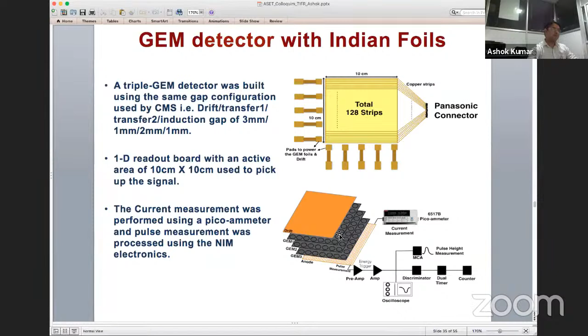And then we also measured the spurious signal rate, which is well within 1 Hertz for the 10 by 10 detector, and this is pretty good. And then we measured the MCA spectrum using the X-ray, and the last one is the gain. The gain is the important test. We have to see whether this is going to work in the region where we have very, very harsh environments. We need a very high rate detector. So we are seeing here that it can handle up to 4 kilohertz, and the gain is 10 to the 4, 10 to the 5.